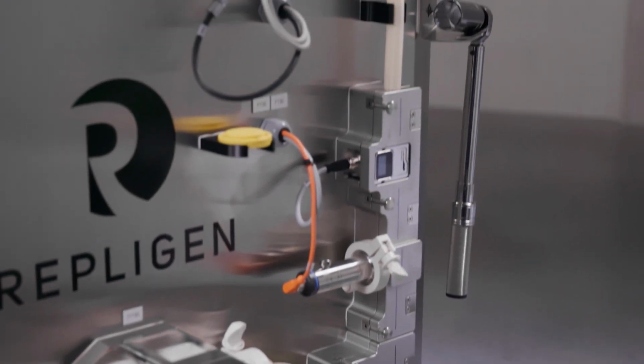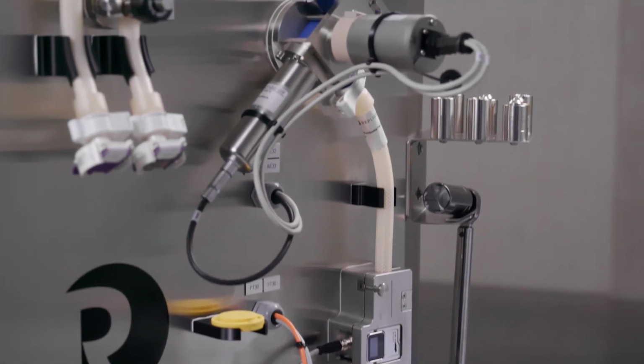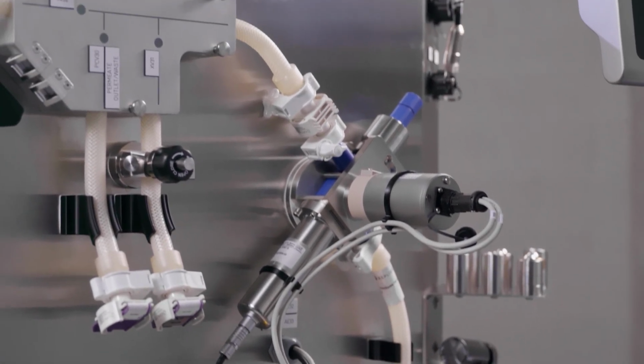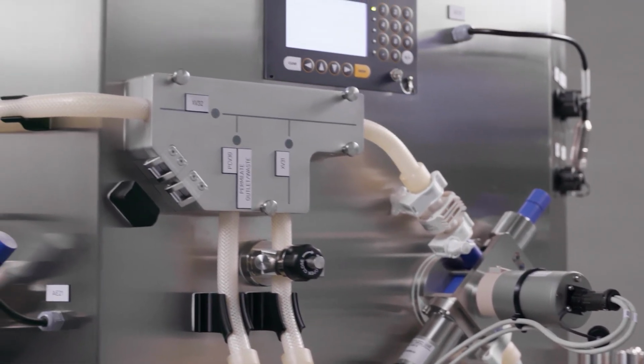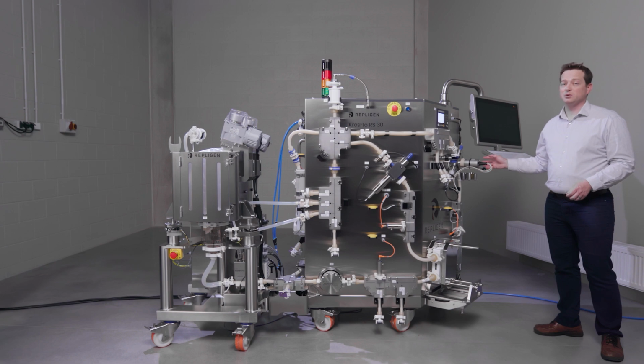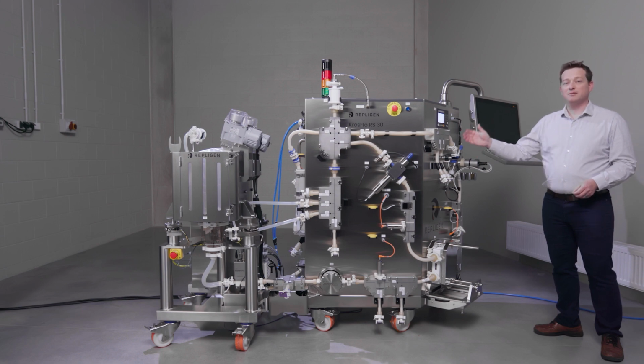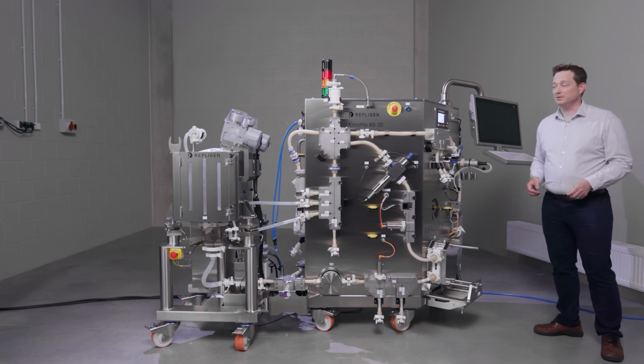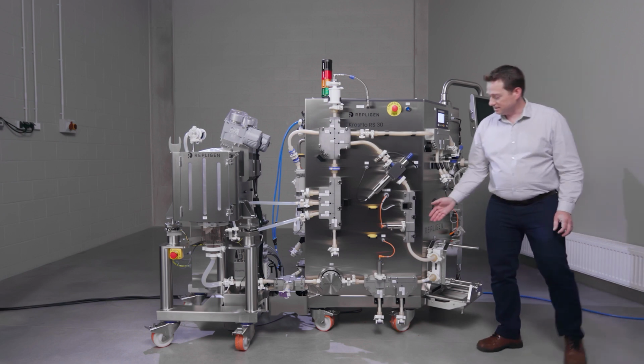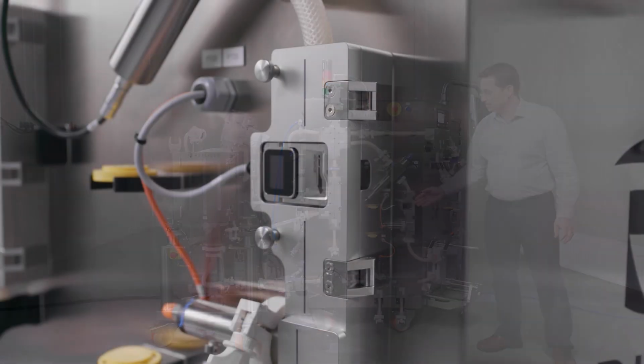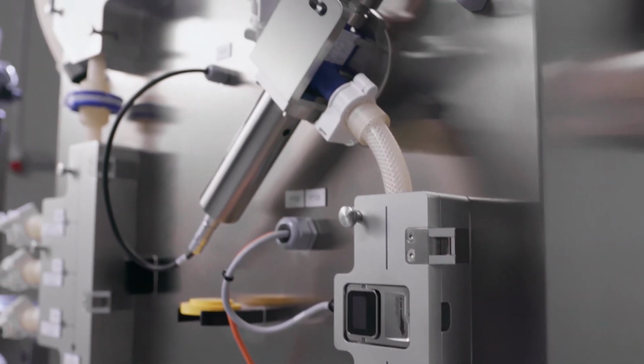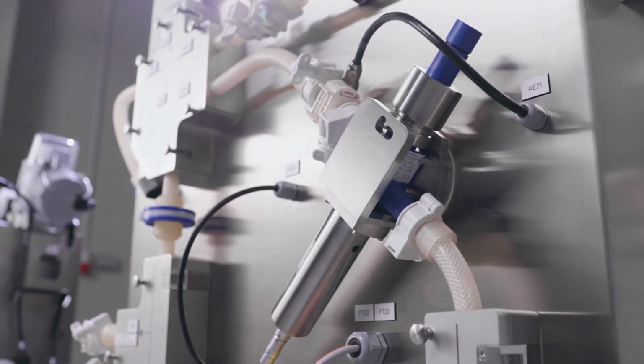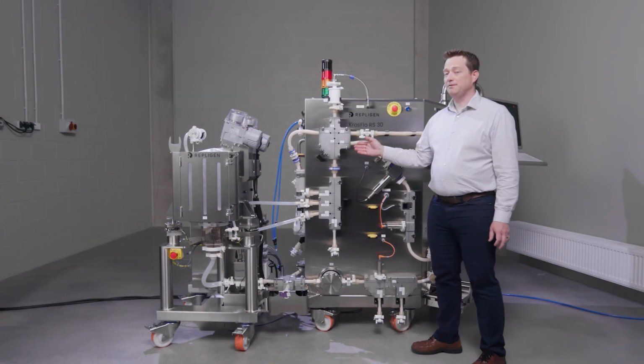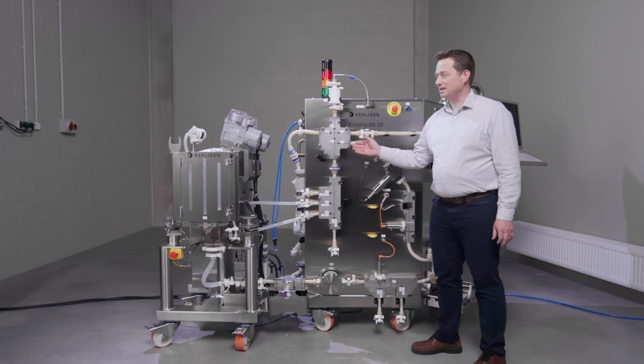The permeate line on the system features a pressure sensor as well as a non-product contact ultrasonic flow meter. It also has conductivity and temperature sensors and optionally a dual wavelength UV sensor and pH sensor. It also supports recirculation and an optional PCV valve for permeate flow control. The retentate line on the system has a pressure sensor and flow sensor as well as optional conductivity and pH sensors. The system uses a precision PCV valve for automated back pressure control on the retentate line.